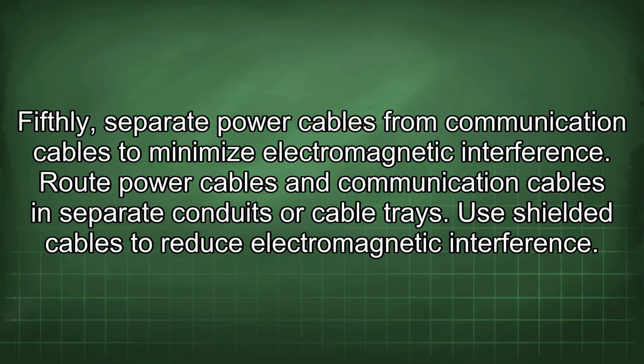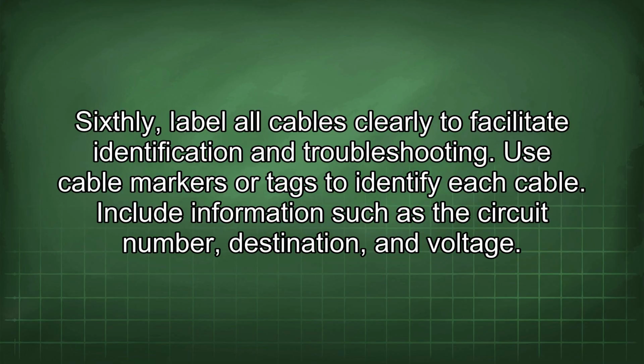Route power cables and communication cables in separate conduits or cable trays. Use shielded cables to reduce electromagnetic interference. Sixthly, label all cables clearly to facilitate identification and troubleshooting.